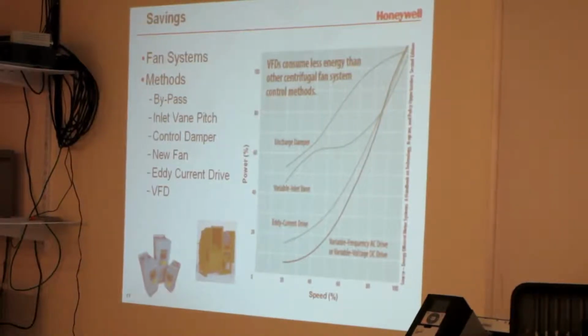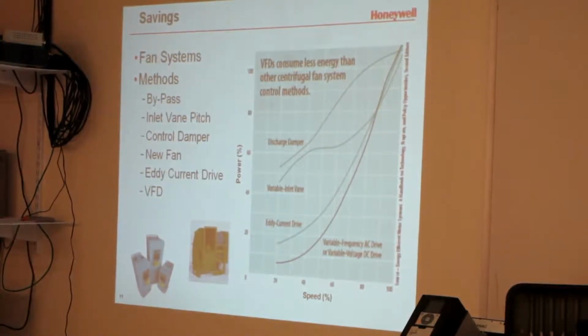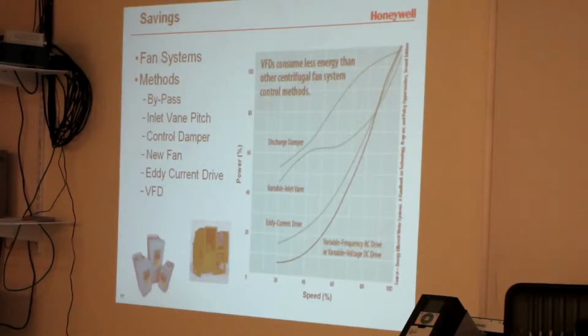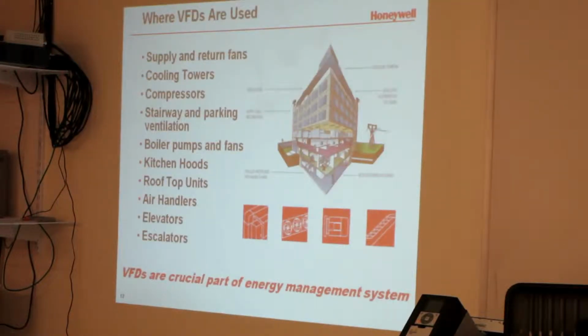You see, the drive is used the least because it's the one controlling the actual power that goes into the motor. Supply and return fans are used. Cooling towers are using VFDs now. One of the issues with cooling towers is where do I put that VFD, because they're not designed to be mounted outdoors.